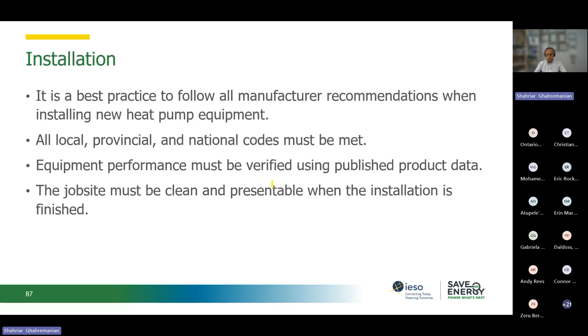Thanks Shariar, a lot of information was covered today. We do have one question that came in earlier when you were talking about water to water systems. I saved it for the end: for an older building with traditional cast iron radiators, using water to water heat pumps to replace the existing boilers, how would you get that last 20 to 30 degrees of heating? Or would you instead try to replace the existing radiators with higher flow, lower temperature models?